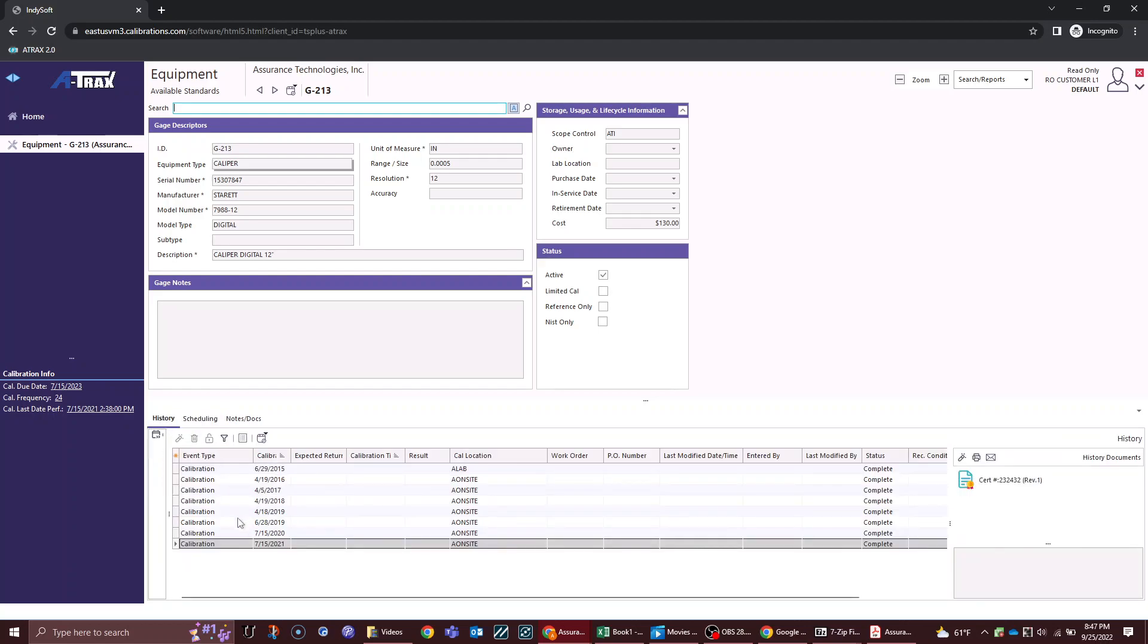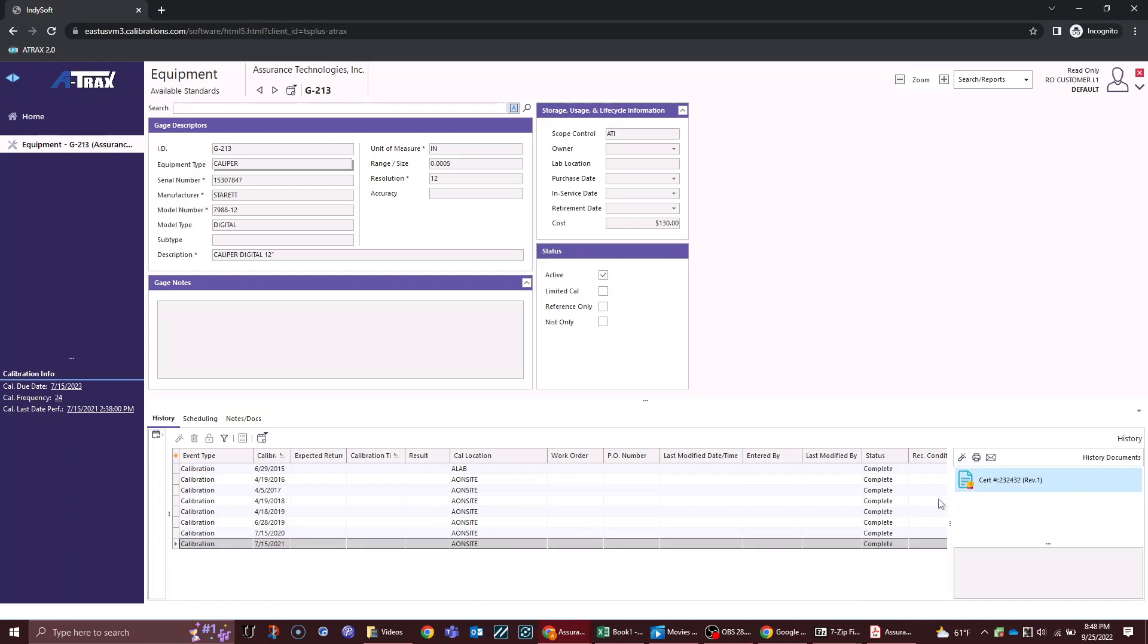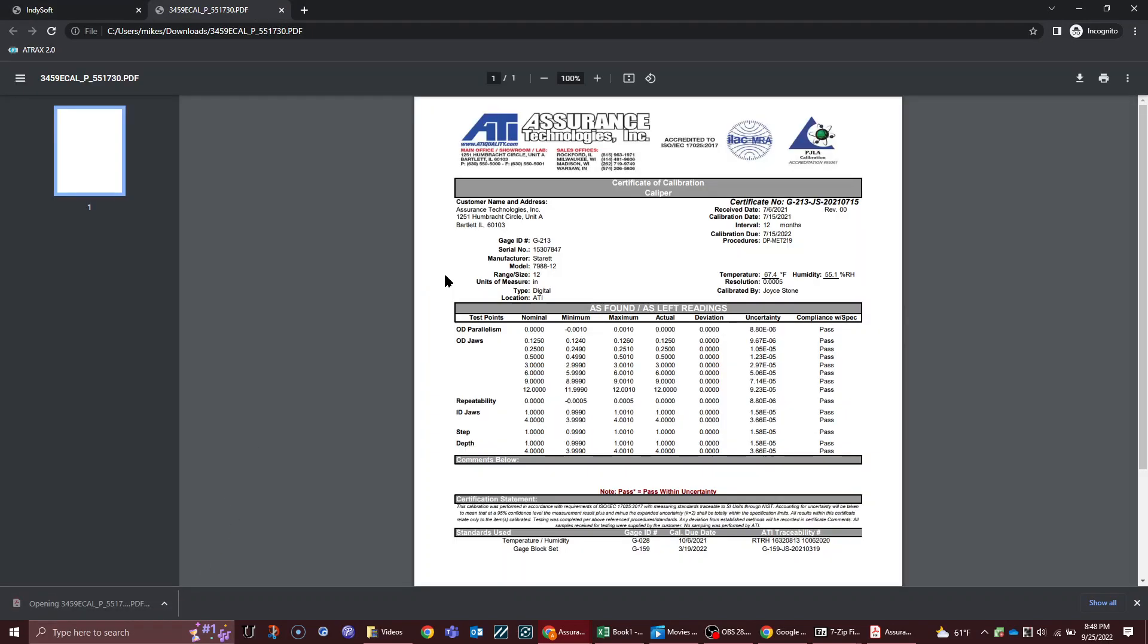Down below we see the history of the gauge and the scheduling. On my history tab I can see that gauge G213 has had calibration events run for the past several years: 715, 2021, 2020, and 2019. Each one of these has a PDF associated with them. If I click on this calibration line event, I have a PDF over to the right that I can double click on, and that will be the actual calibration PDF for that calibration.